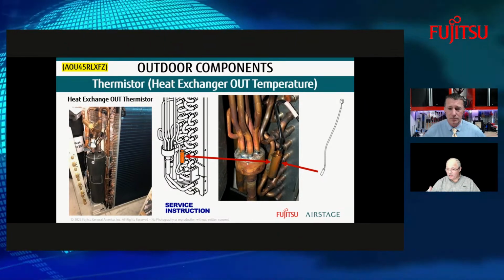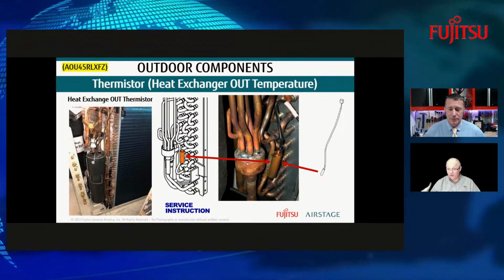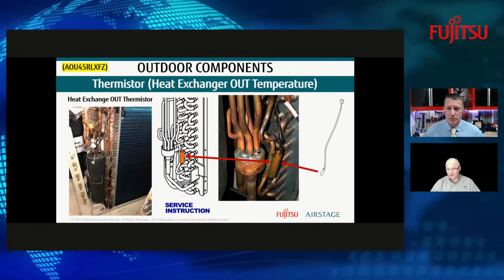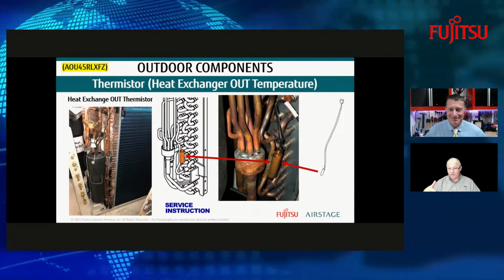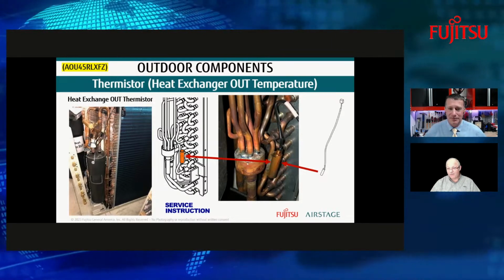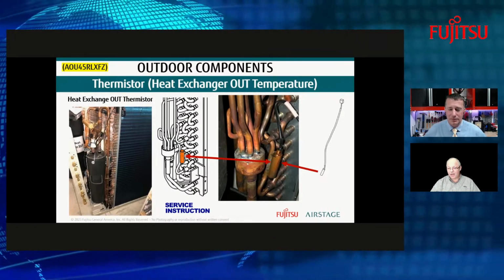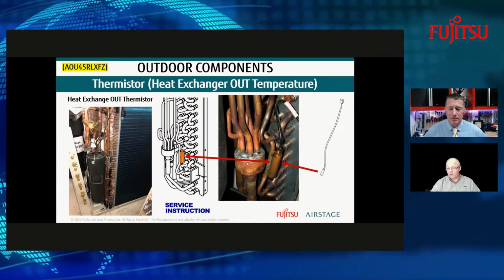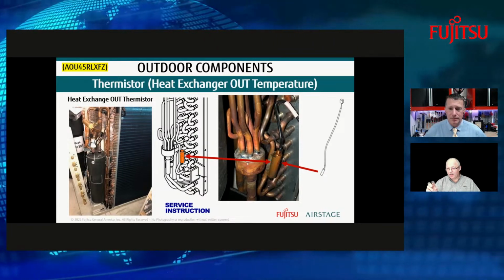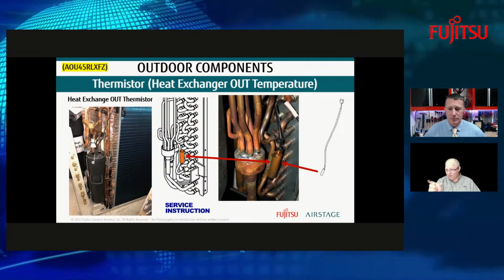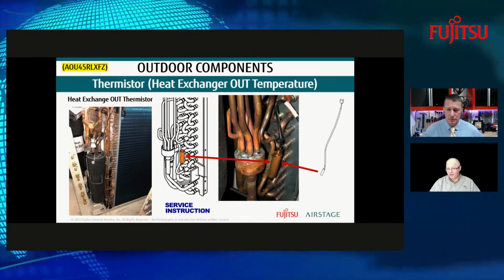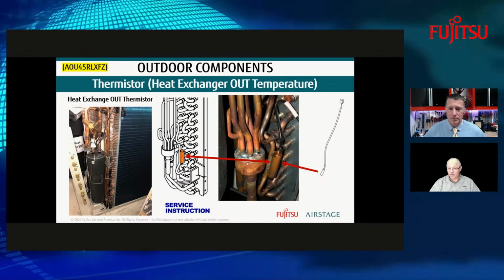So if your outdoor coil gets dirty, and it just keeps getting dirty, and grass gets in it, and the dog lays around it, eventually you could have another thermistor shut the system down. But we're trying to see what the subcooling number is and see if we're still matching up to our range that the system's programmed to run within on subcooling.